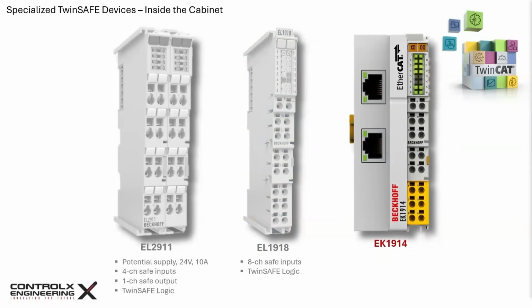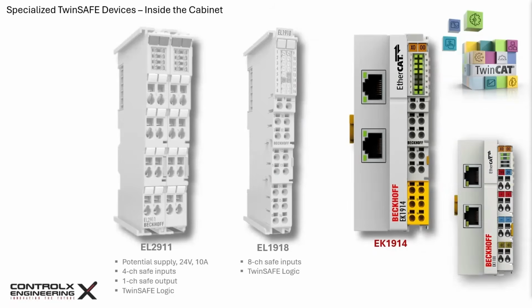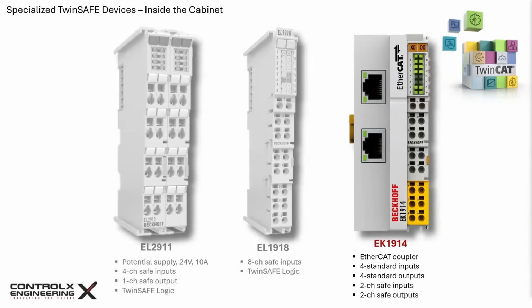The next combination terminal I want to highlight is the EK1914. If this looks familiar, that's because it's a variant of the EK1100 coupler. The EK1100 is an EtherCAT coupler that enables formation of separate stations with any number of EtherCAT terminals that are automatically detected and individually displayed in the process image. The EK1914 combines the function of the EK1100 EtherCAT coupler with 4 standard digital inputs and 4 standard digital outputs, as well as a 2-channel safe input and 2-channel safe outputs. The EK1914 does not feature TwinSAFE logic functionality, thus a separate logic terminal will be required.